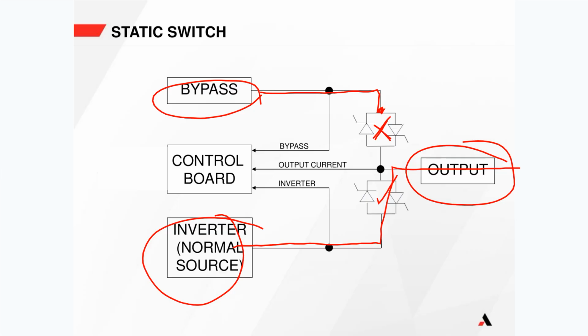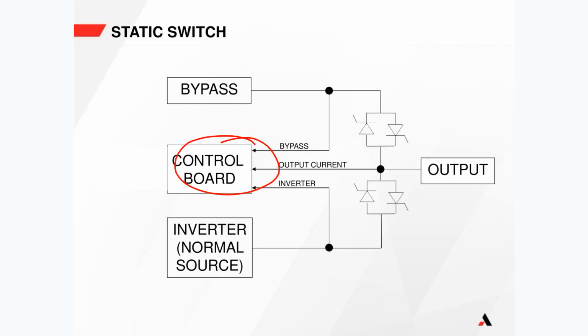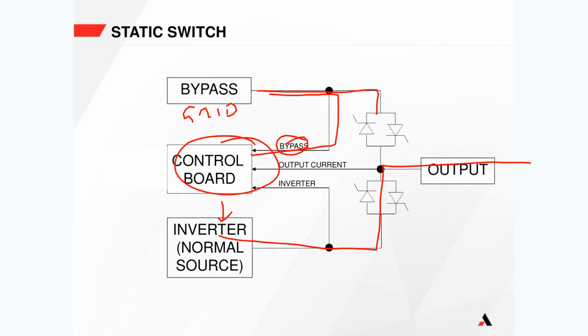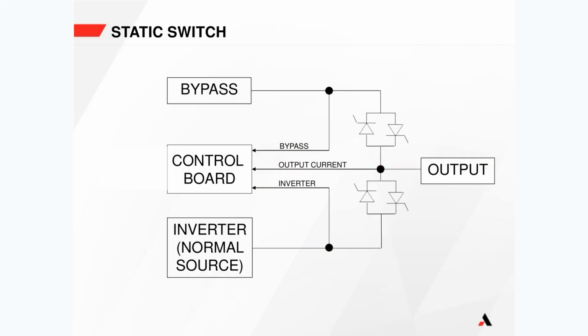Now, obviously, the control board is looking at the bypass, okay? And what it says is, okay, I'm going to monitor this bypass because I want to be in synchronization with that bypass. I'm going to tell the inverter to synchronize with the bypass, which is coming from the grid, okay? So therefore, when the inverter is on and going out through this way here, the bypass on this side of the static switch is in synchronization with the inverter.